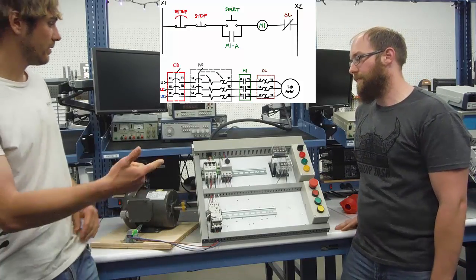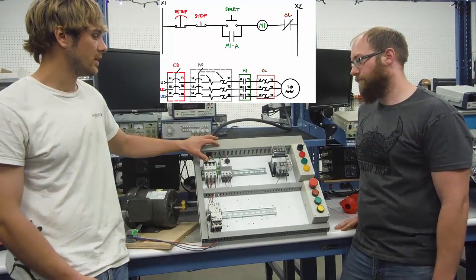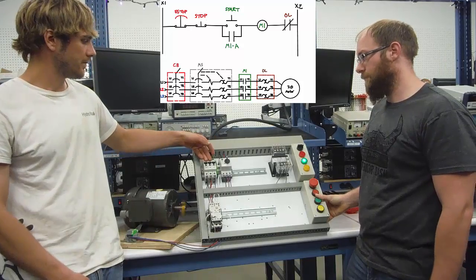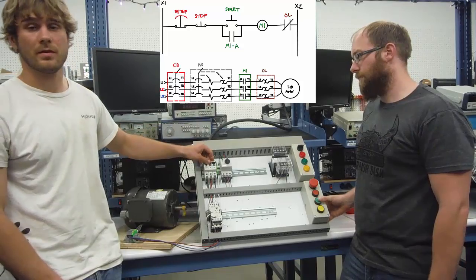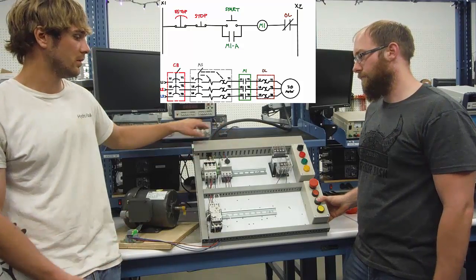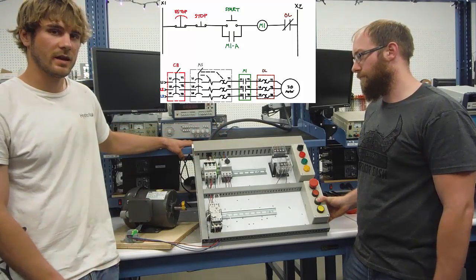So when the motor is turned on and there is a sudden loss of power, the motor will shut off. But it won't turn back on when the power is restored until the green button is hit again.